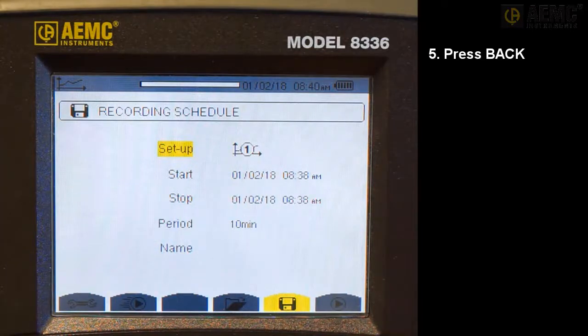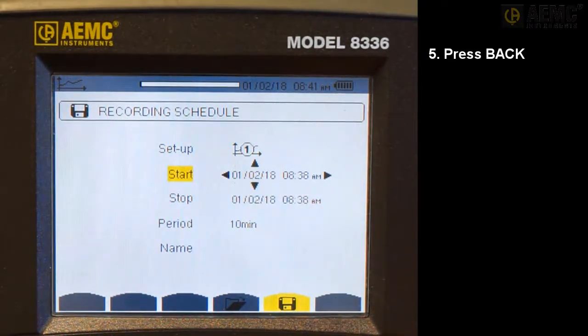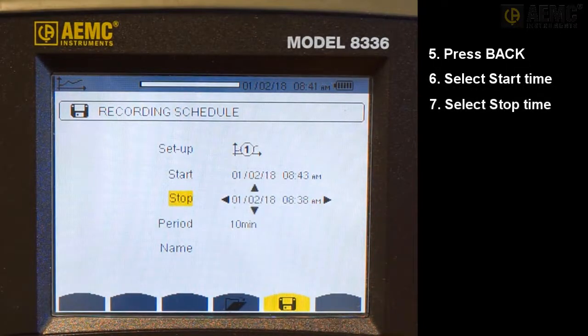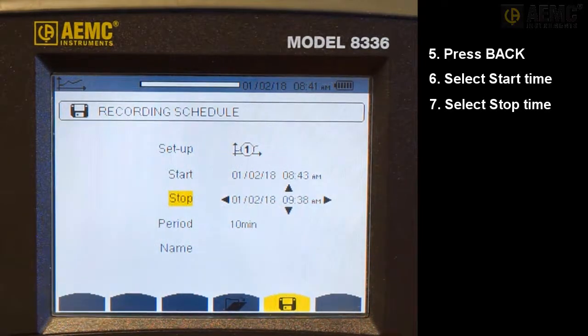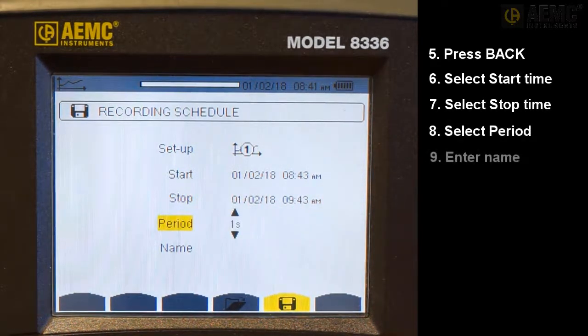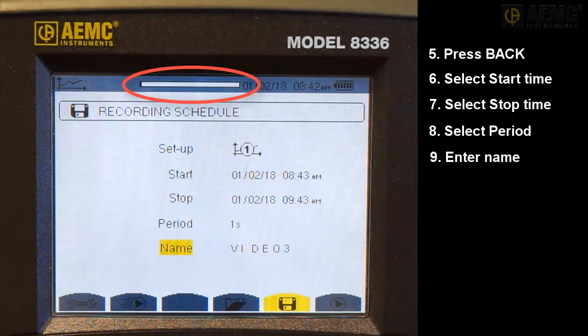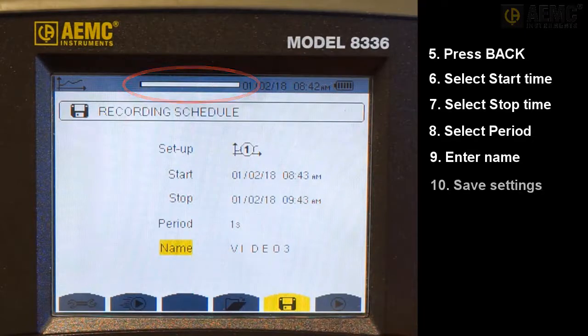Use the arrow and Enter buttons to highlight, select, and edit the Start and Stop fields. For our demonstration, we will set Start for a few minutes past the current time, and stop one hour past the start time. We will also set the period to one second, and give the recording the name Video 3. Note the Memory Usage bar at the top of the screen. This indicates how much memory is available for storing recordings. If this indicates little free memory remains, return to the Recording List screen and delete one or more stored recordings. Press the last yellow Function button on the right to write the settings to the instrument.